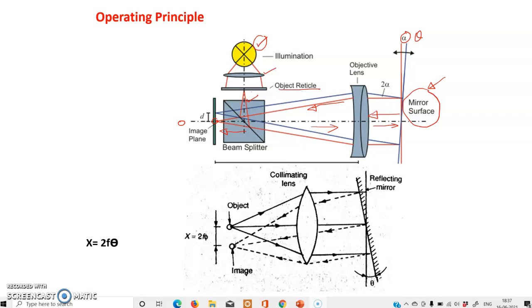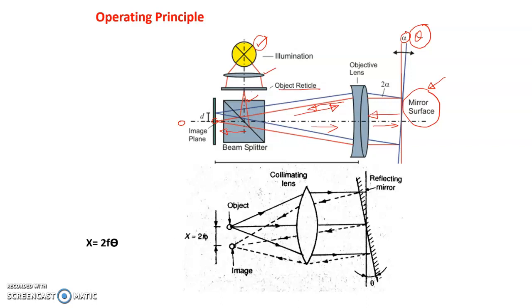In the second part, if we provide an angular tilt of theta to the mirror surface, the beam will move in the same direction as in the first case, but after hitting the mirror surface it will be reflected back at an angle of 2 theta to the first beam. It will pass back through the collimating lens and through the beam splitter, and it will be incident on the image plane at a different point known as O dash. The distance between O and O dash is denoted by x. If we can measure this distance x, we can relate x with respect to the deflection theta and the focal length of the collimating lens.